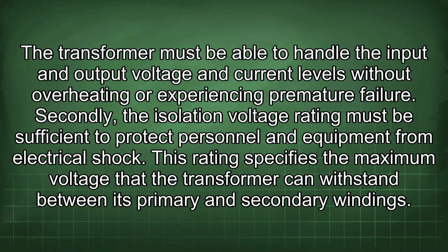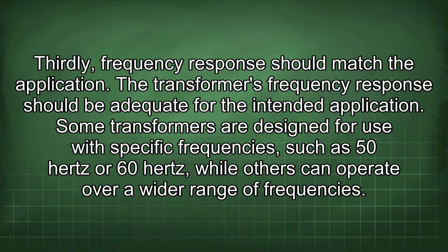The transformer must be able to handle the input and output voltage and current levels without overheating or experiencing premature failure. Secondly, the isolation voltage rating must be sufficient to protect personnel and equipment from electrical shock. This rating specifies the maximum voltage that the transformer can withstand between its primary and secondary windings. Thirdly, frequency response should match the application. The transformer's frequency response should be adequate for the intended application. Some transformers are designed for use with specific frequencies, such as 50 Hz or 60 Hz, while others can operate over a wider range of frequencies.